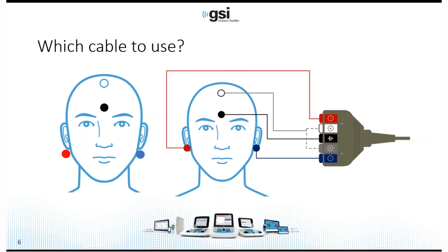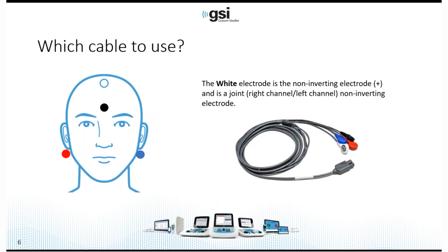If you want to use the 5-lead cable, you would need 4 electrode leads and a jumper cable. So the jumper cable would connect the positive of each channel, right and left channel, and you would plug that electrode lead to the top of the head or the white, just like the 4-lead cable, except you'd be using a jumper cable as well. This cable can be used for all test types, so it really would depend on your preference, except remember that with the snap lead cable, you cannot use any specialty electrode, only the disposable snaps.